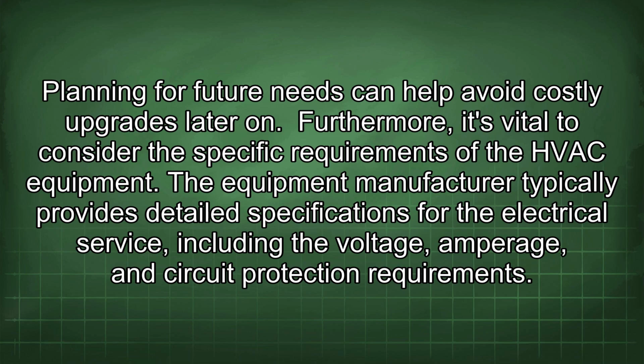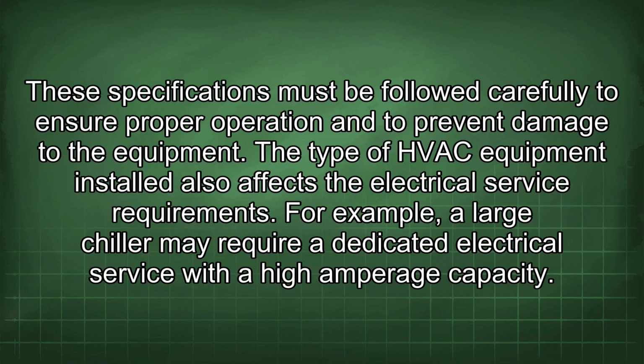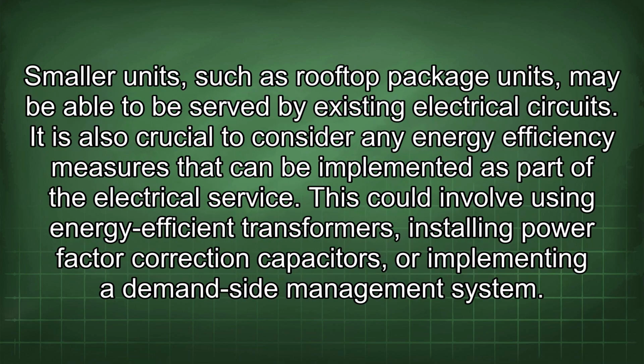Furthermore, it's vital to consider the specific requirements of the HVAC equipment. The equipment manufacturer typically provides detailed specifications for the electrical service, including the voltage, amperage, and circuit protection requirements. These specifications must be followed carefully to ensure proper operation and to prevent damage to the equipment. The type of HVAC equipment installed also affects the electrical service requirement. For example, a large chiller may require a dedicated electrical service with a high amperage capacity. Smaller units, such as rooftop package units, may be able to be served by existing electrical circuits.